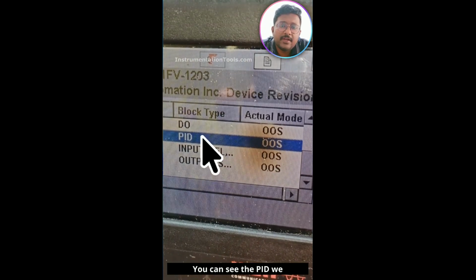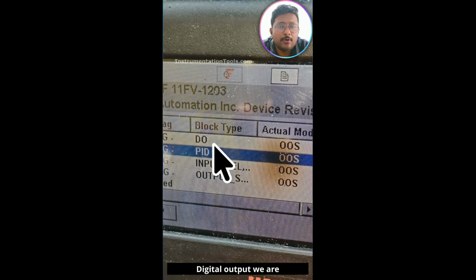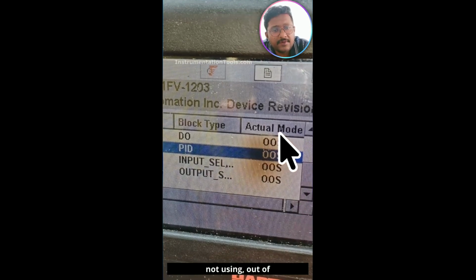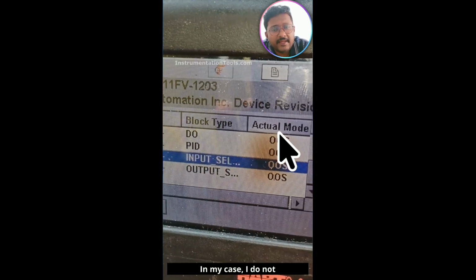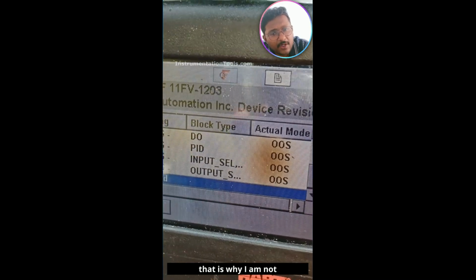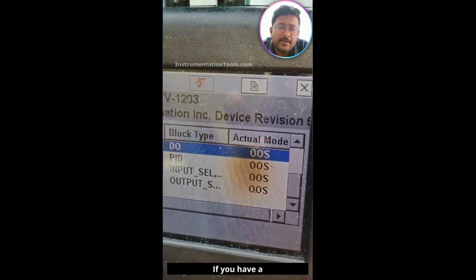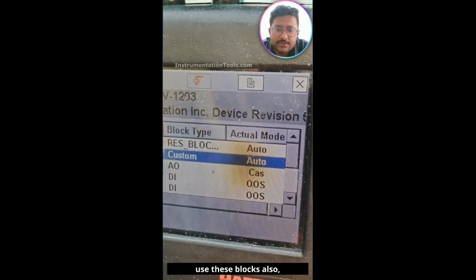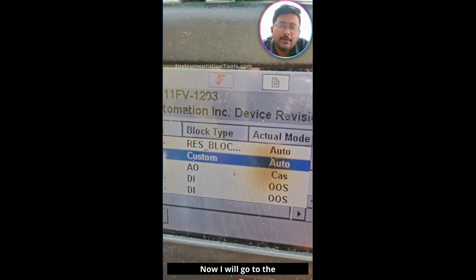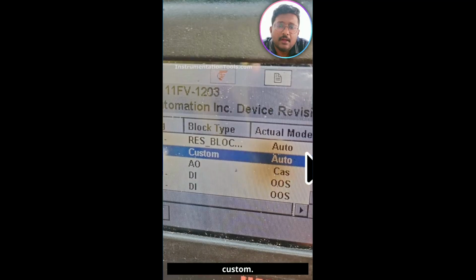You can see the PID we are not using here, out of service. Block type DO, digital output, we are not using, out of service. In my case, I don't have any requirement. That is why I'm not using it. If you have a requirement, you can use these blocks also, no issue. Now I will go to the custom view. I need to go to the transducer block to do the calibration.